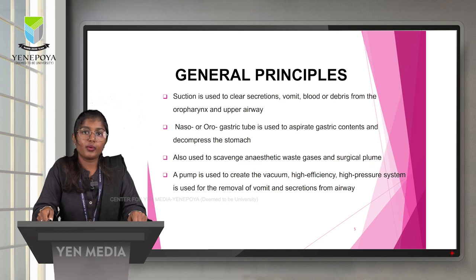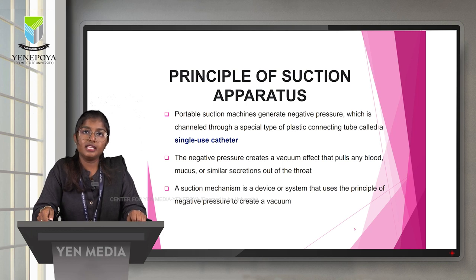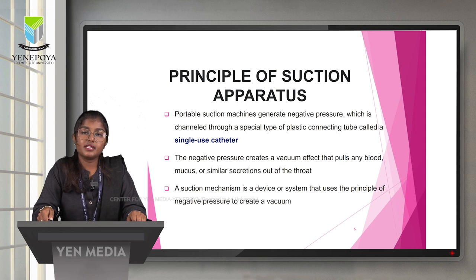A pump is used to create the vacuum. High-efficiency, high-pressure systems are used for the removal of vomit and secretions from the airway. Portable suction machines generate negative pressure, which is channeled through a special plastic connecting tube called a single-use catheter. The negative pressure creates a vacuum effect that pulls blood, mucus, or similar secretions out of the throat.